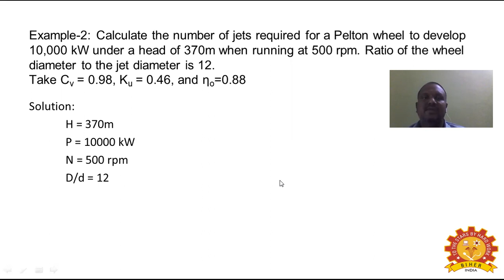First, the number of jets is the total discharge, capital Q, divided by the discharge of one jet, small q. Q can be found from the relation P equals density Q g H into efficiency. So 10,000 is equal to 1000 into Q into 9.81 into 370 into 0.88. Calculating, Q is 3.13 meter cube per second.